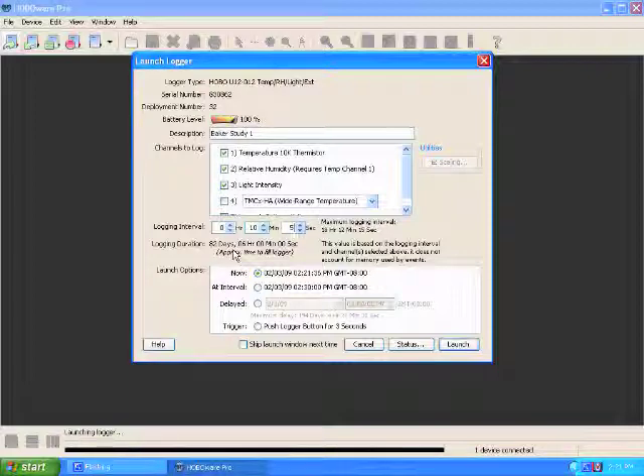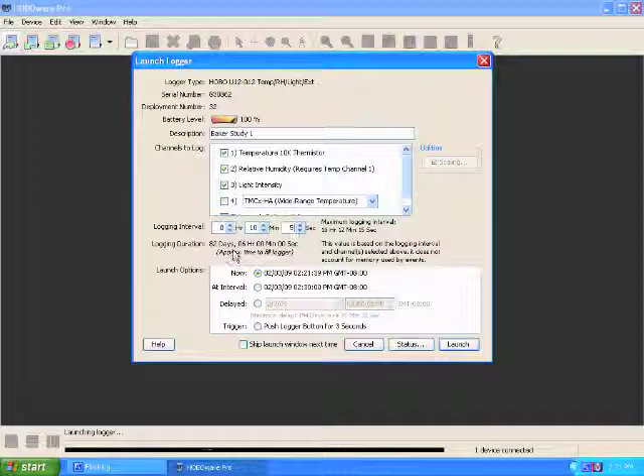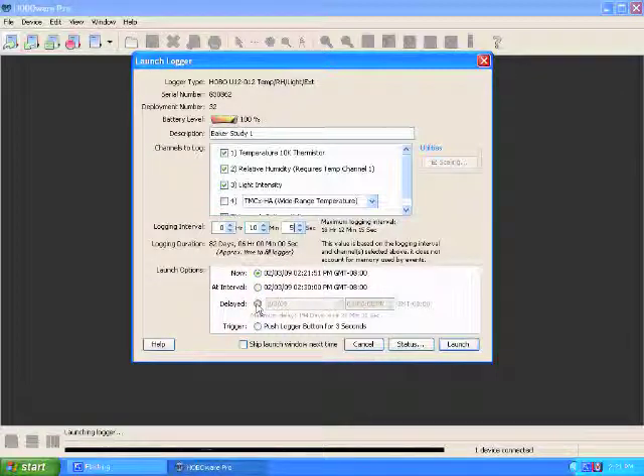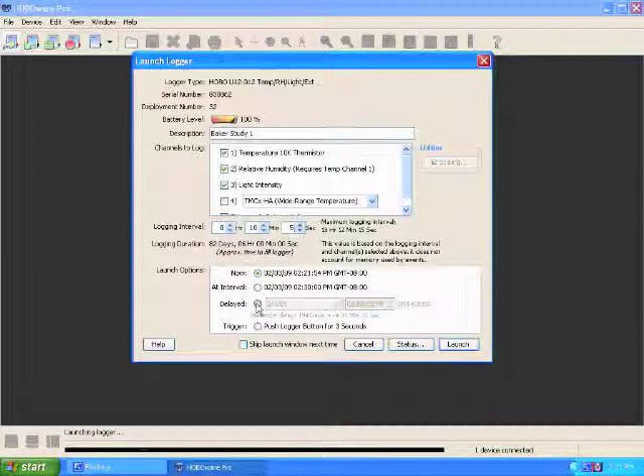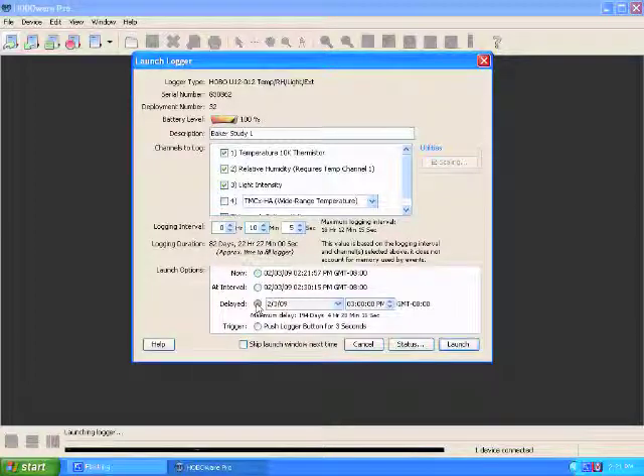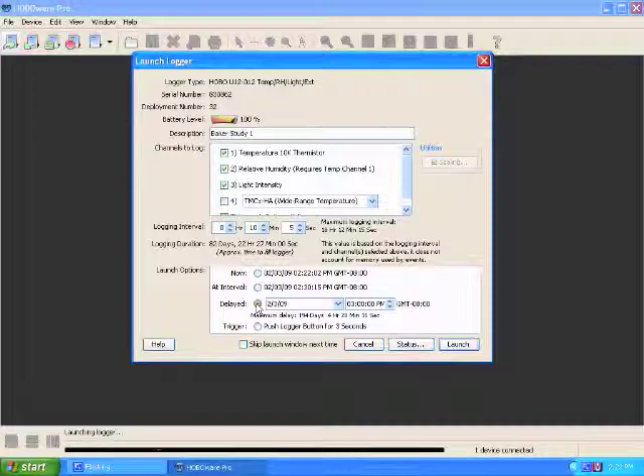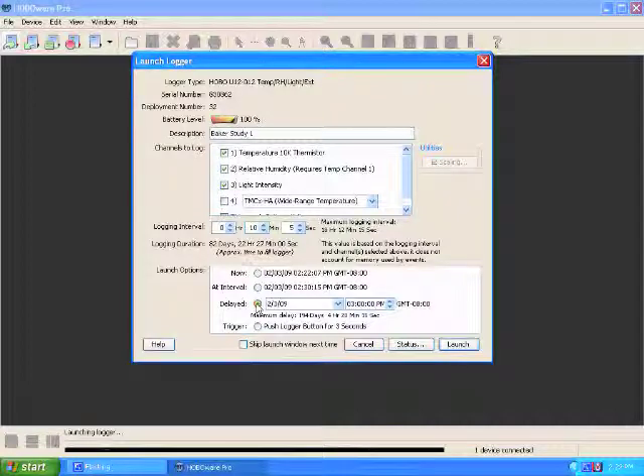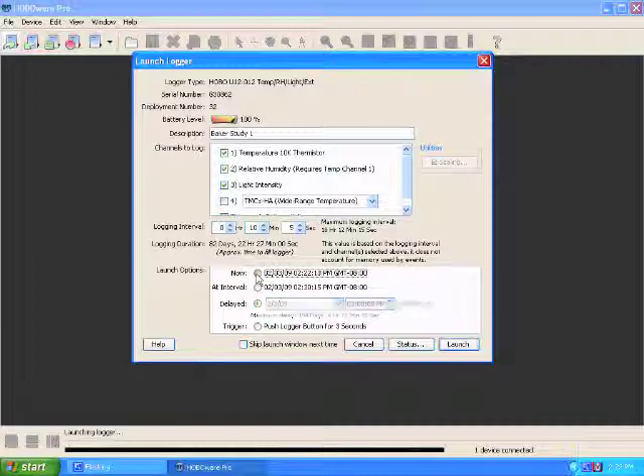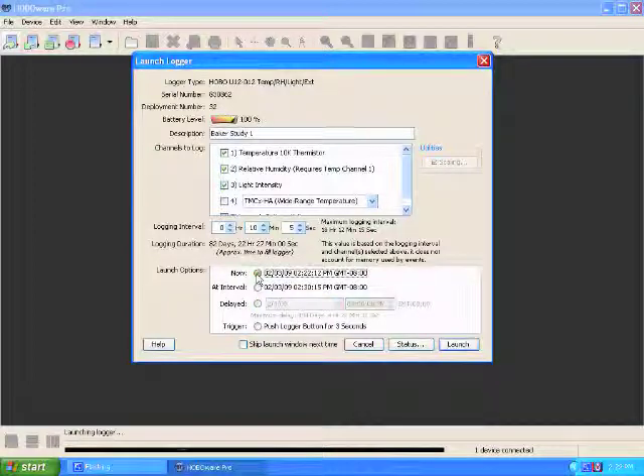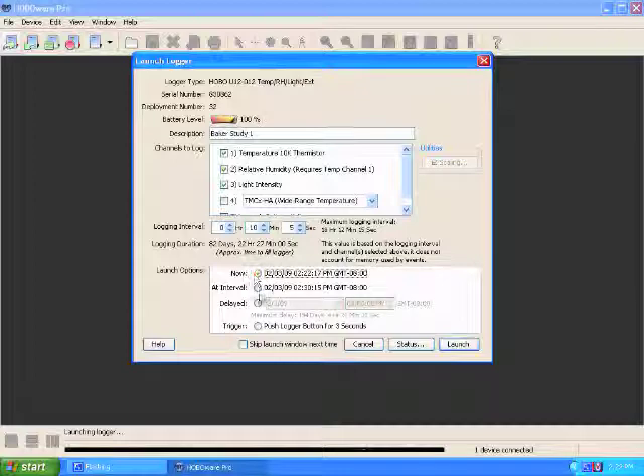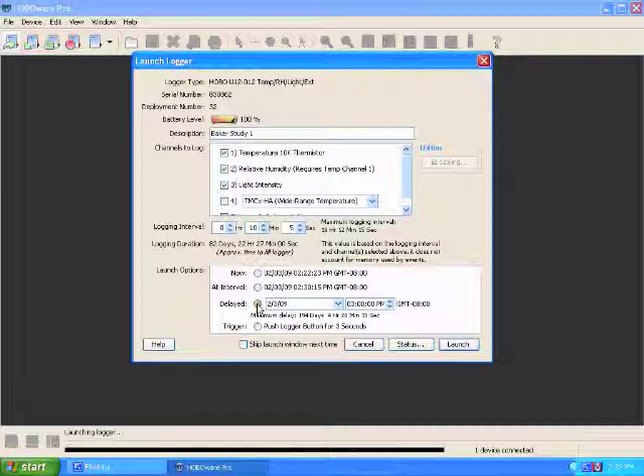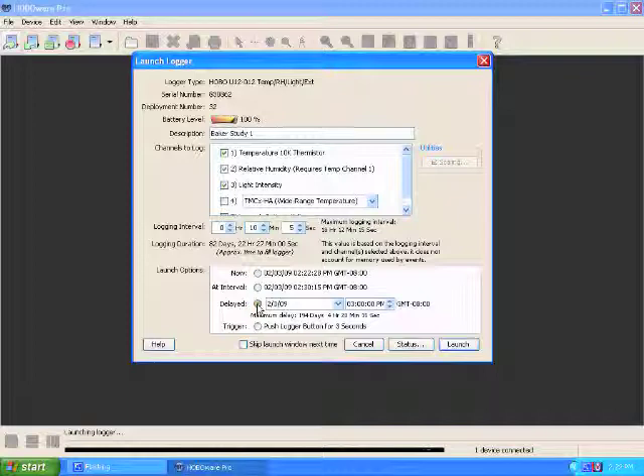This box here allows you to choose when you launch your data logger. Here, you want to pick the delayed start if you are launching multiple loggers. This is important because if you're launching multiple data loggers, you want them to start at exactly the same time. And so when you're launching them in order from your computer, if you choose this option, you will get data sets that start at different times, even if they have the same interval. So if you choose the delayed start at an exact time, your data sets will all line up and will make your charts a lot easier to work with and a lot easier to find correlations between your data.